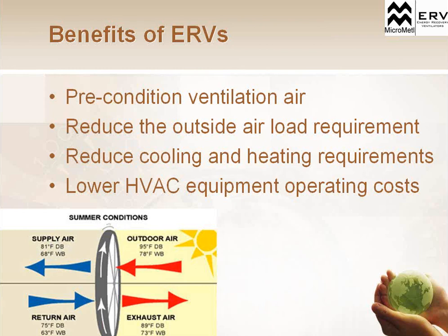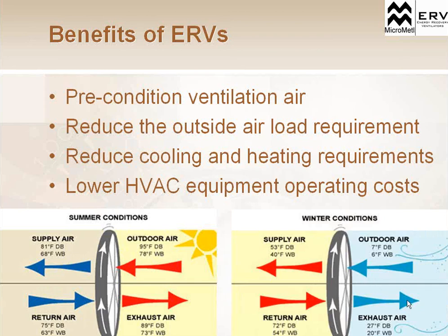We're not burning any fuel source, or using any energy to actually heat or cool the air with compression. We're just using energy from the building, from that exhaust air, to pre-cool that outside air coming in. Now, conversely, if we look at the winter situation, an ERV is used year-round. This is not just a seasonal piece of equipment.